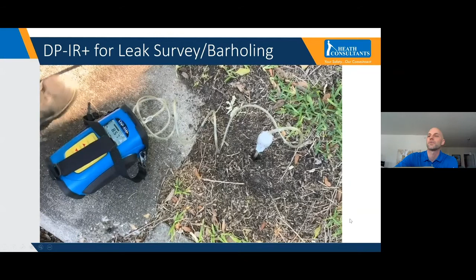Okay, so that video kind of showed you some of the methods of using it. I mentioned the walking survey and then bar hole testing. You can see the quick response time that it got on the alarm. It sounds like the sound may not be working on that, so I guess we'll try to improvise. Anyway, the video itself still showed what I was trying to show: the instrument being used for walking survey. You saw the numbers on the screen went up, and then it transitioned into Roy using the below ground probe for taking a subsurface reading.